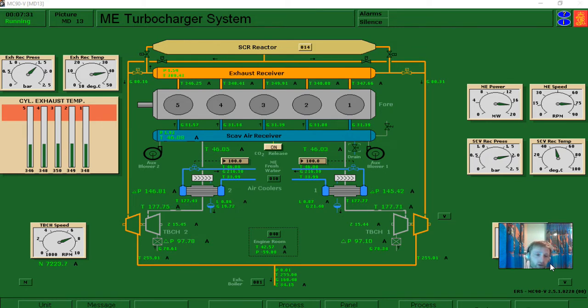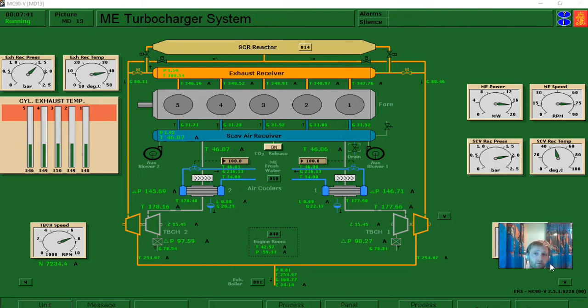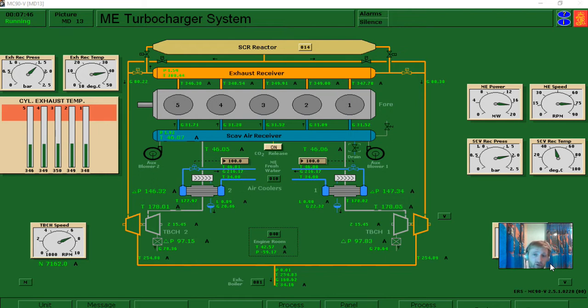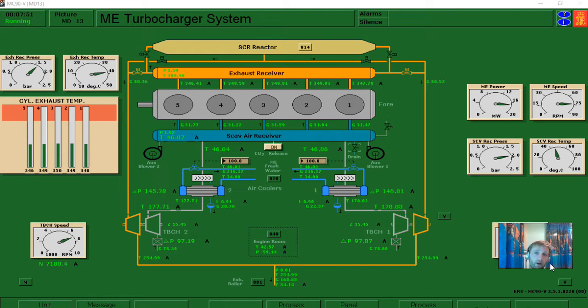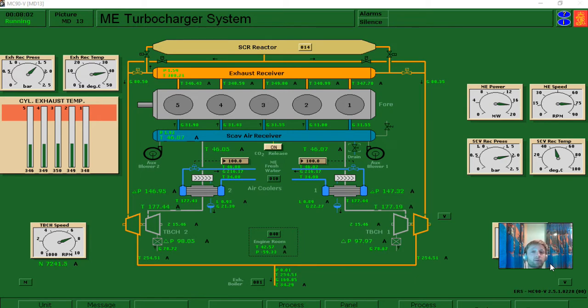Normally all the temperature sensors have deviations, that is true. If you have such measurements between the electronic indication inside the control room and the local one, you have big differences. First of all you need to calibrate all the necessary instruments so you have a better idea what is going on inside your engine.